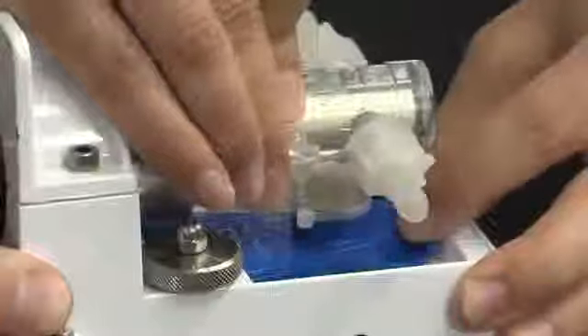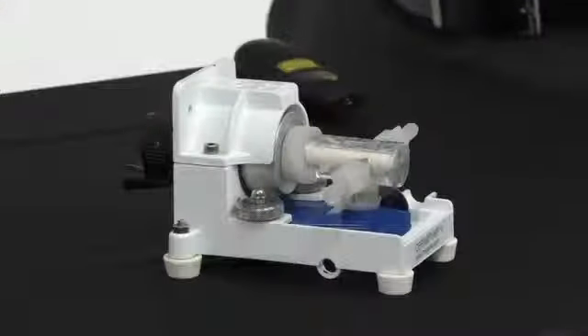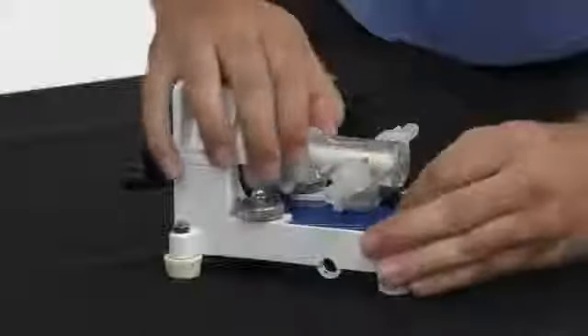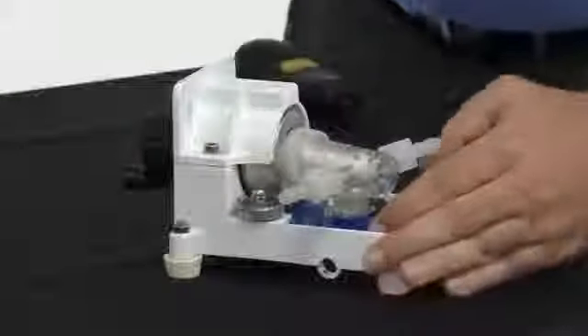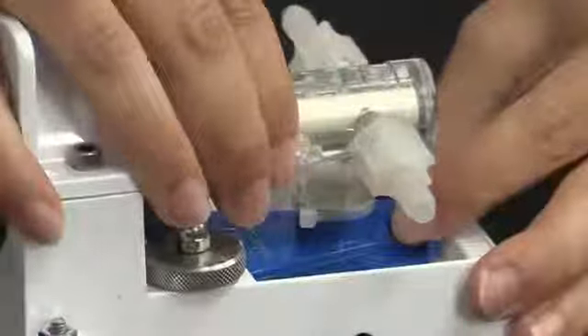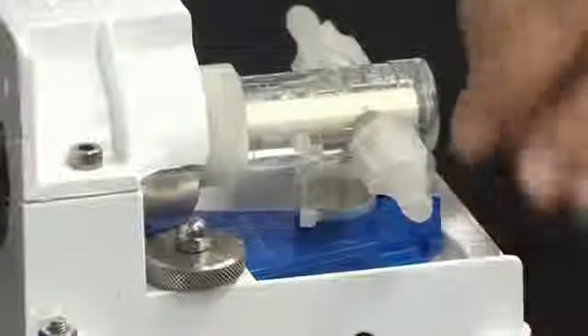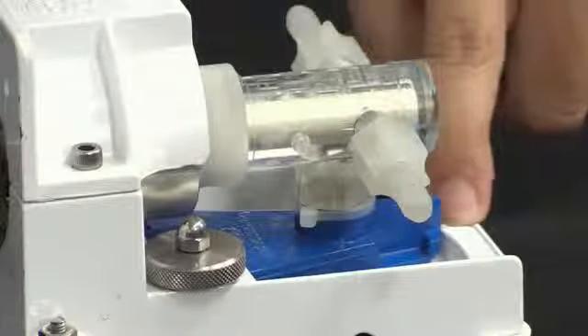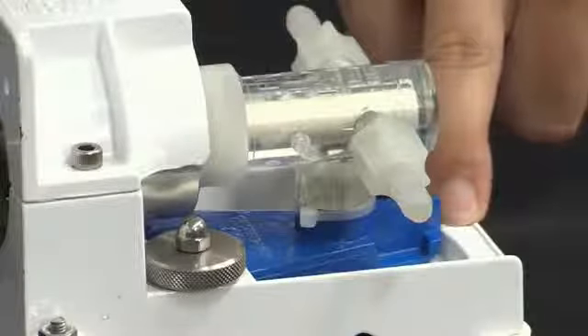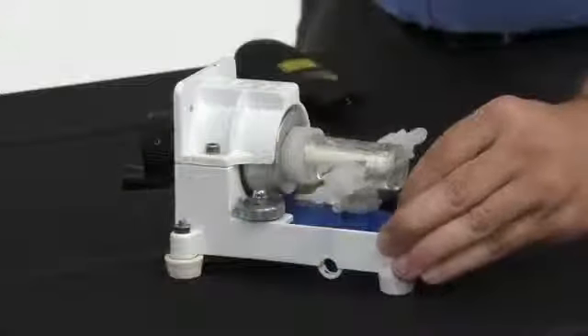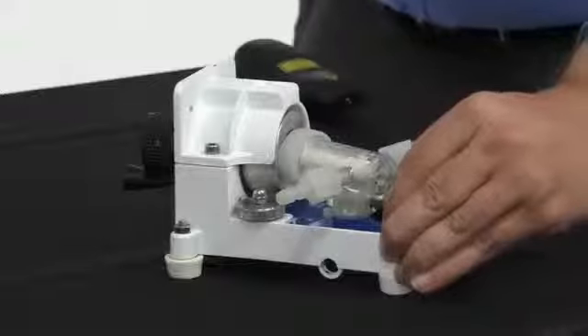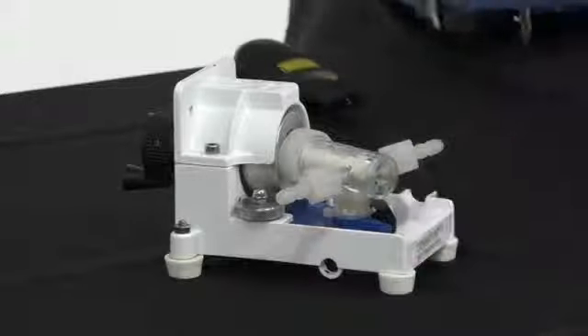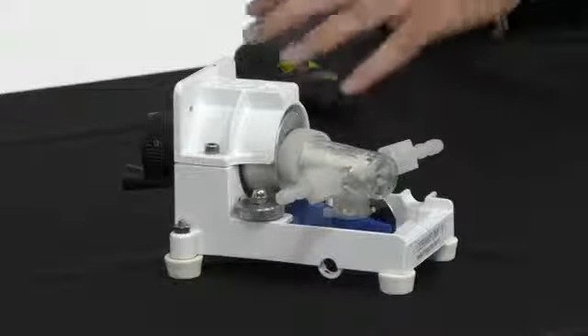What would you use that for? The reason is you can actually vary how much the pulse delivers by changing this angle. It's just like a fine tune. Oh, I see, so it's almost like a calibration. Yeah. If I set it to, say, the centre, the flow rate drops, and if I move it further and further out, the pulses and the flow rate will increase. Okay, so you've got kind of two levels: this movement and the RPM.